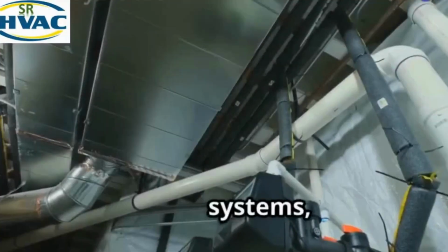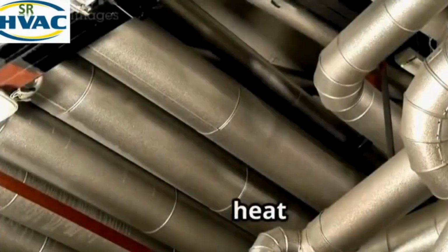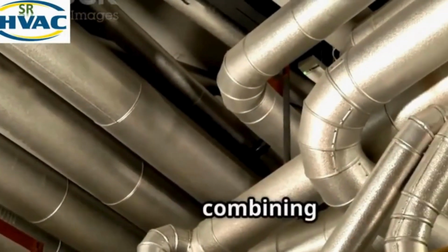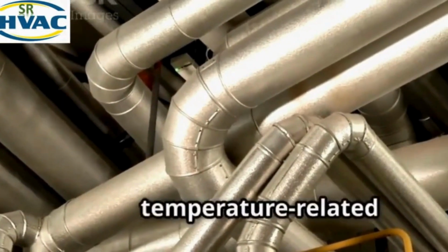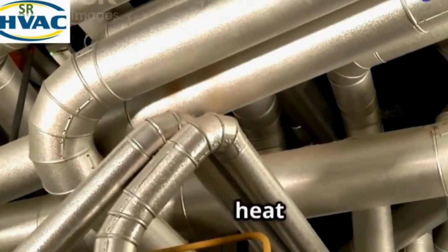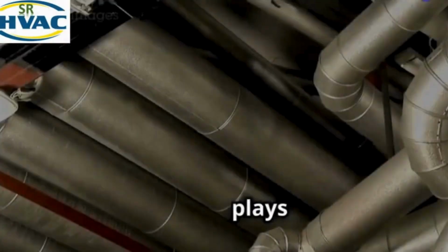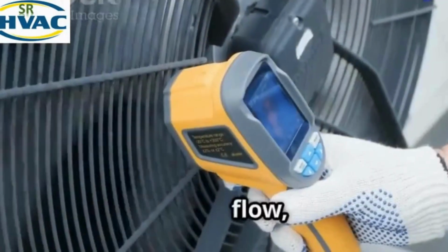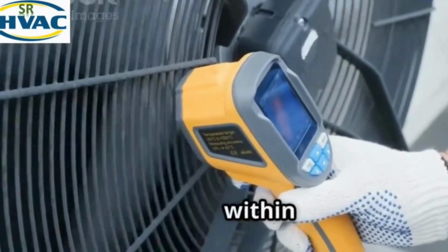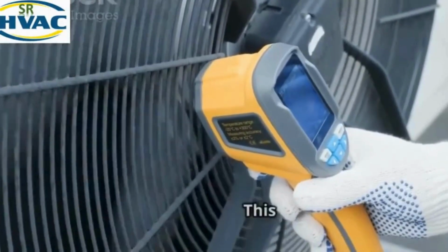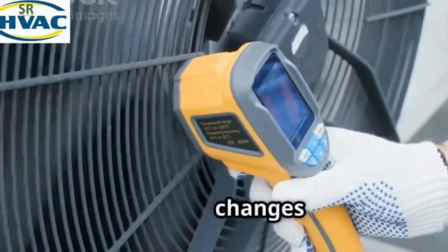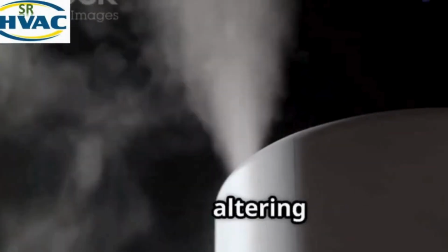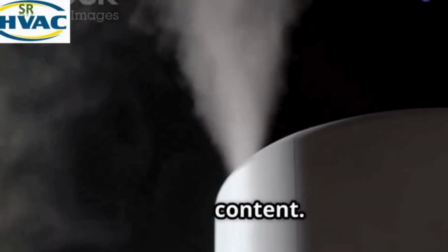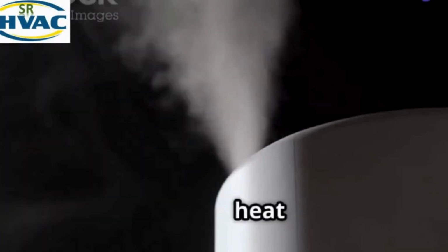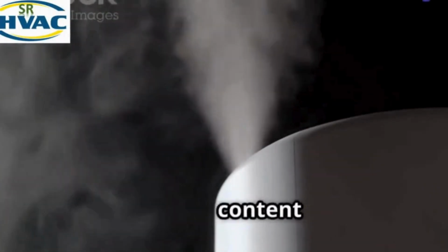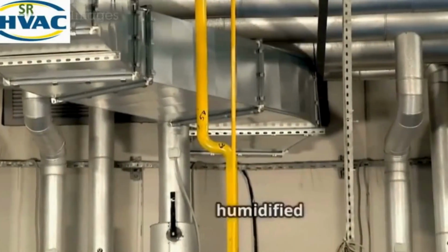In HVAC systems, enthalpy is the total heat content of air or fluid, combining both the sensible heat, temperature-related, and latent heat, moisture-related. It plays a crucial role in managing energy flow, heating, and cooling loads within a building. Sensible heat. This is the heat that changes the temperature of the air without altering its moisture content. Latent heat. This is the heat involved in changing the moisture content in the air, like when air is humidified or dehumidified.